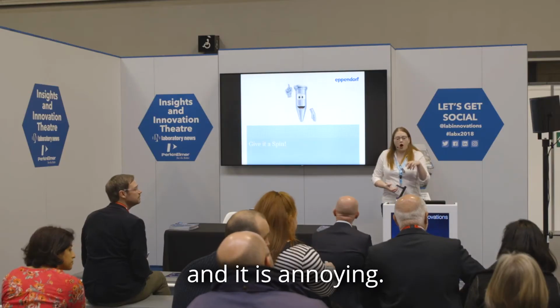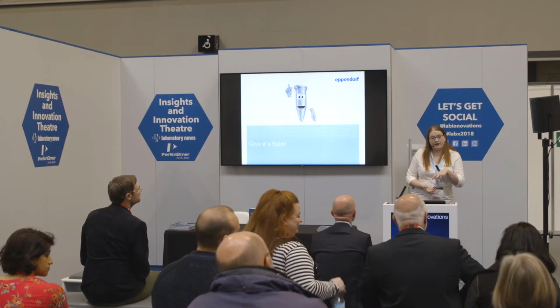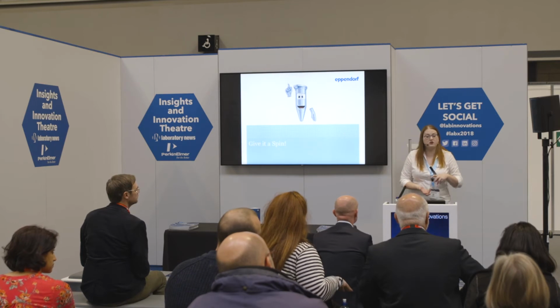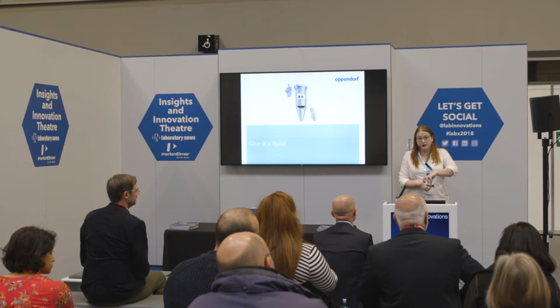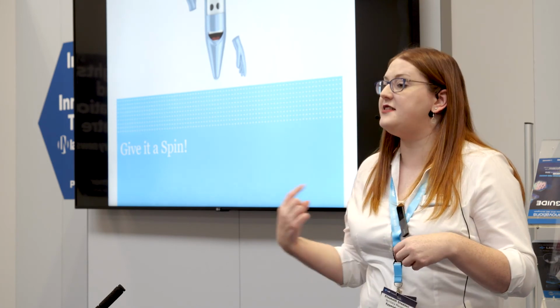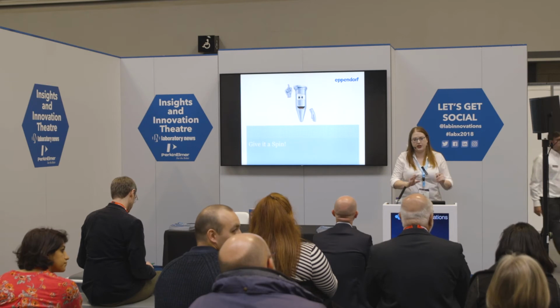So ours aren't click lids, but we have something called click lock on the newest ones, where you only have to turn the lid through 90 degrees to make it aerosol tight. It doesn't click on, but it's only a 90-degree twist - a quick lock rather than having to screw them down. A lot of the older ones you have to screw down, which can often lead to the seals getting damaged because people over-tighten them. But the newer ones have click locks, so you can't do that.